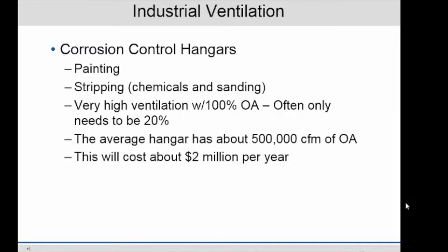Because this particular one, 500,000 CFM of outside air was about $2 million a year to heat and cool that hangar. And they had to heat and cool, because for painting, you need cooling. If you're just stripping, all you need to do is heating. But for painting, they heat and cool 24 hours a day, 365 days a year. So there's a big opportunity for savings on these corrosion control hangars.